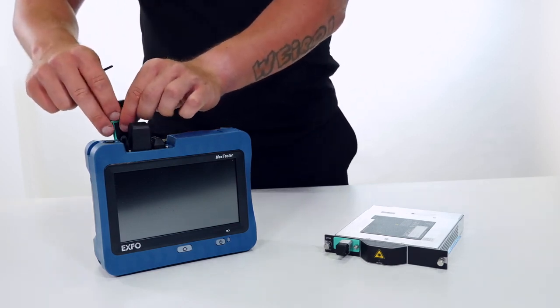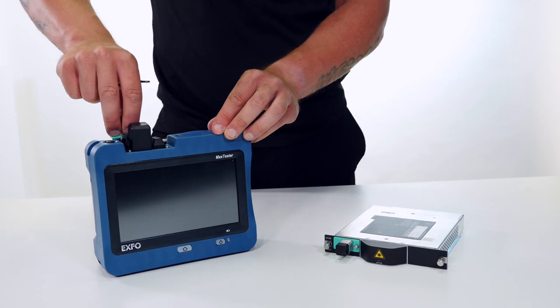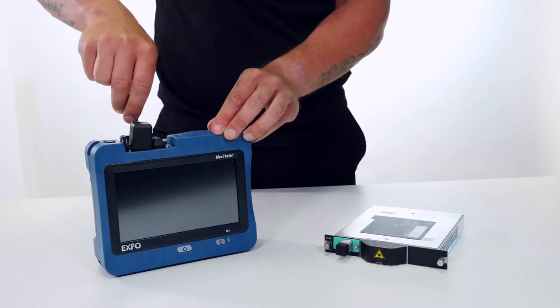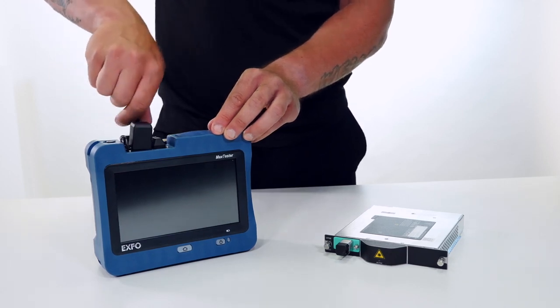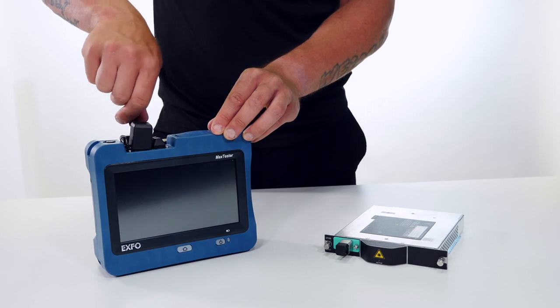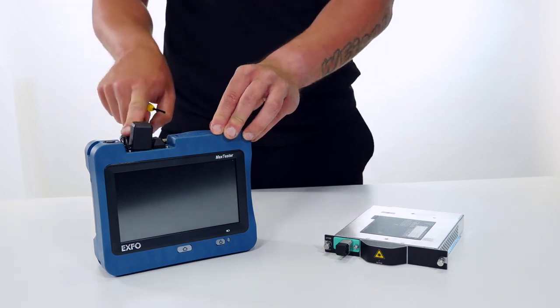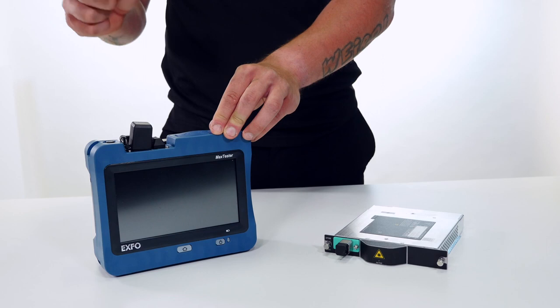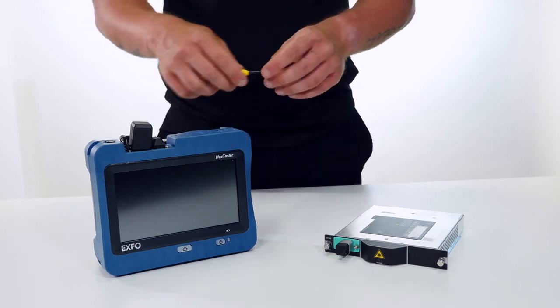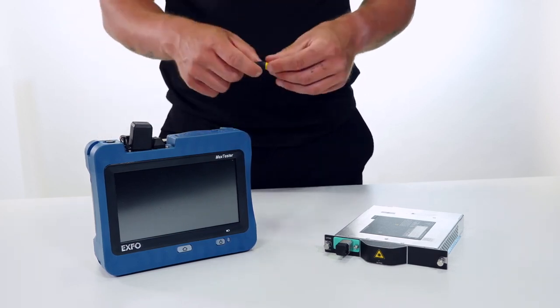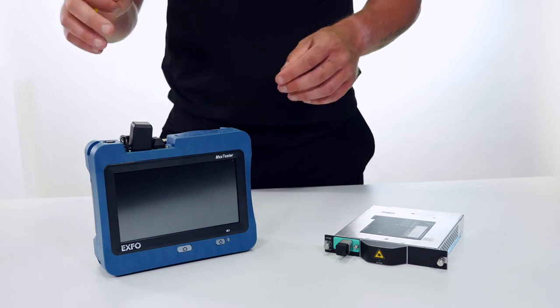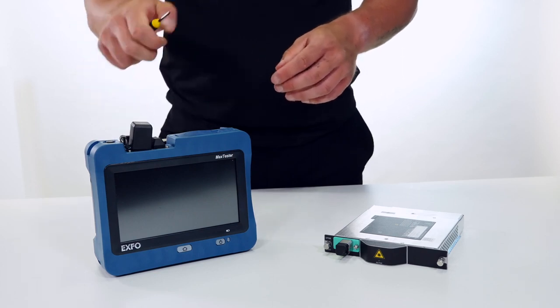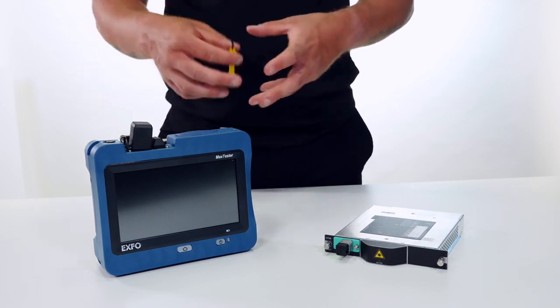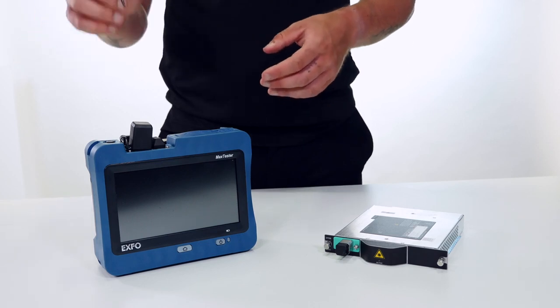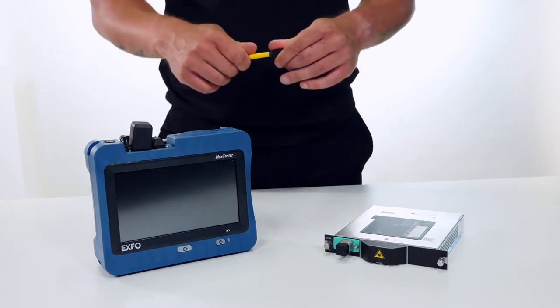For the Max tester to install, we just have to slide it in and then tighten up the screw once again. The reasons we might want to change the swap out connector is if the external connector has been damaged from multiple connections or just from overuse, then we can swap the connector without having to affect our calibration date. If the internal connector becomes damaged, that's when we need to send the device into a service center to change and calibrate the internal connector itself.